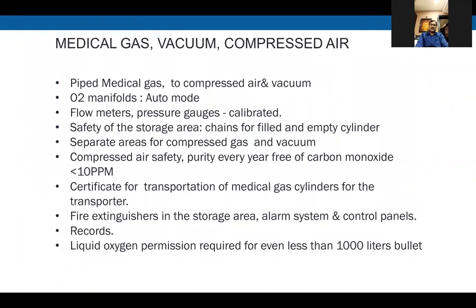So now I'll come to another important topic, medical gases: vacuum and compressed air. These you will generally find in the basement or in the adjoining area of the hospital, or behind the hospital or on the sides of the hospital, and generally they are neglected, because safety requirements, which are very, very important, are to be maintained from the patient safety point of view. I have mentioned specifically auto mode. Most of them are not in auto mode. Manually, they have to be controlled.